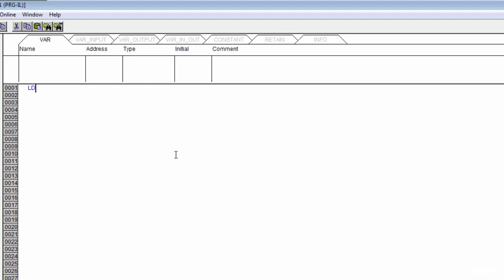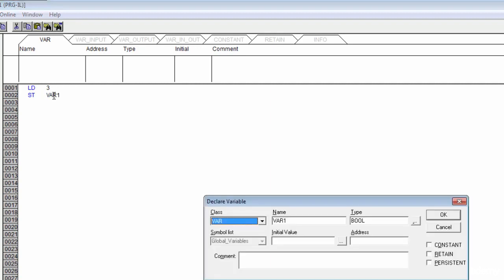LD means load. So I'm going to start by loading some kind of value and I will go ahead and load the value three. So now I'm loading a three. And now that I've got a three loaded, think of this as basically you've got a plate in front of your face where you would normally put some food. You can only have one thing on this plate at a time. So I just put a three on our plate. Maybe I want to store that into a variable. So I'm going to type ST and then I'm going to store that into VAR one. And now I can define my VAR one and I'll go ahead and call that an int.